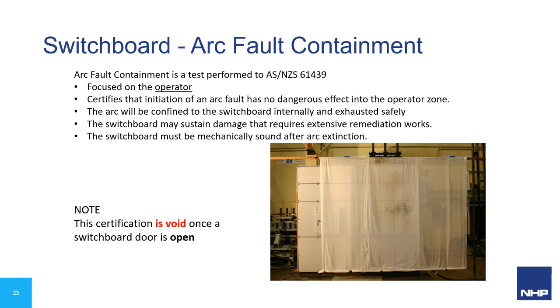The requirements for this is that it has no dangerous effect to the operator zone. The arc's confined to the switchboard internally and it's exhausted safely. The switchboard may sustain damage that requires extensive remediation works, so you still need that clean up. But the switchboard must be mechanically sound, so you can't have any doors falling off or anything like that.